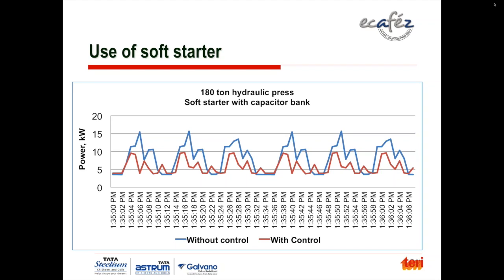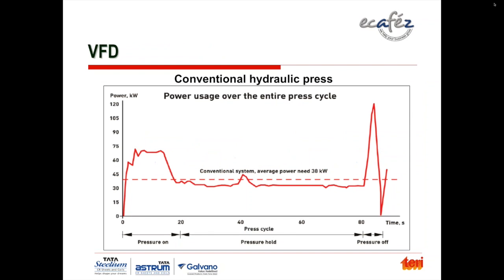We have recorded this actually, before and after cases, and you can see the red line. That is how the power curve is after you have a soft starter and capacitor bank, and basically the area between those two is the power saving. So this is a huge amount of power saving, and also the peak power reduction which can happen through that.